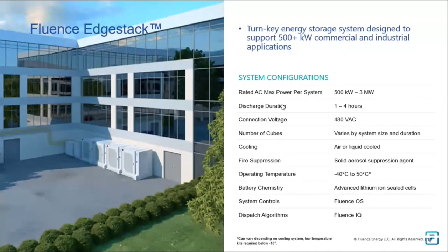Okay, and what exactly do these batteries do? So what we do is deploy the battery in parallel to your grid connection. These battery storage systems are always synchronized to the grid frequency. When there's an outage, the software automatically shifts the source of power from the grid to battery storage. Since it's already synchronized, you can be up and running in less than 250 milliseconds to feed the load.